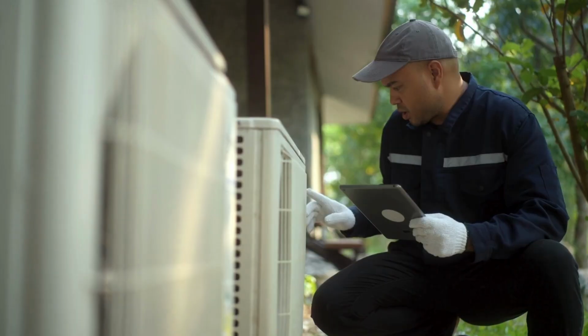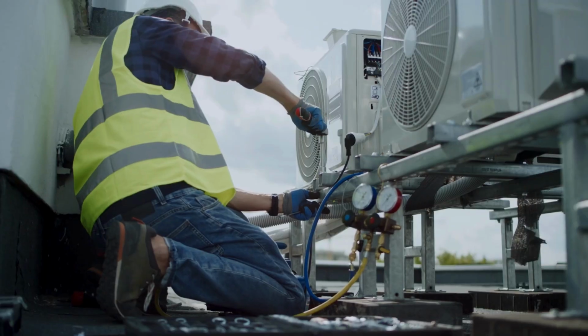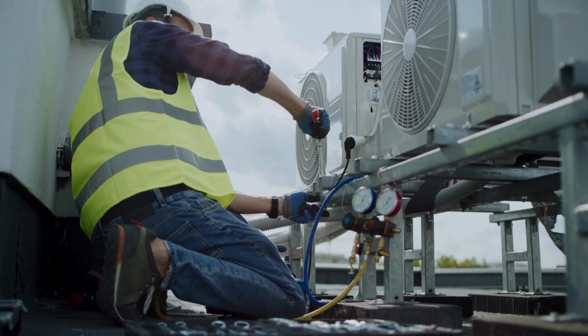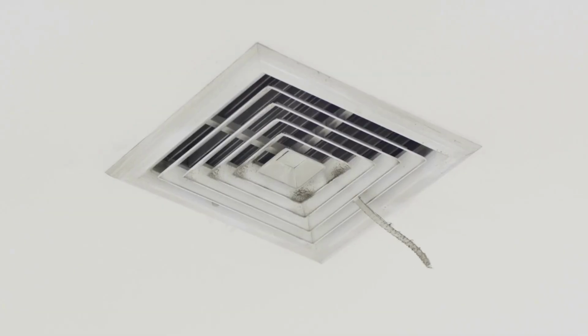I got a call from a homeowner whose 3-year-old system was already failing. When I arrived, I found their blower motor was overheating and their compressor was showing early signs of failure. The culprit? It was static pressure. That static pressure was nearly double what it should have been. Their system was essentially having a constant heart attack. It was working way harder than it needed to, just to push air through clogged filters and undersized ductwork.